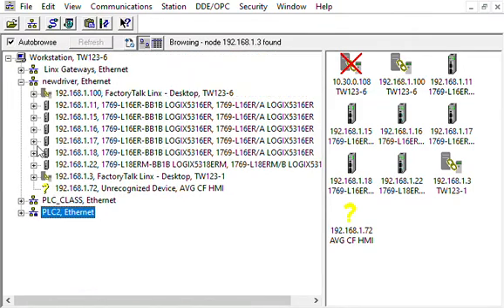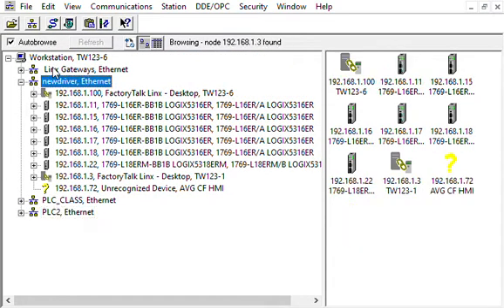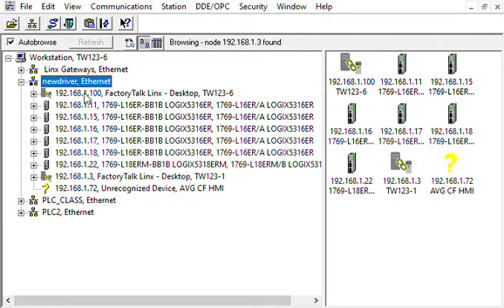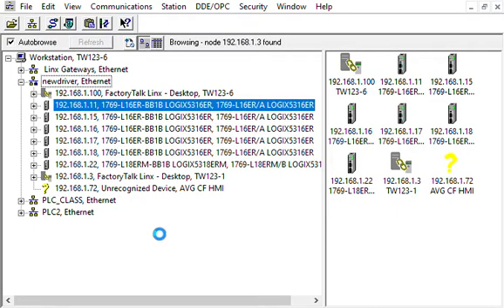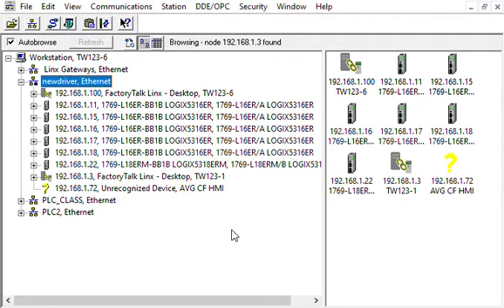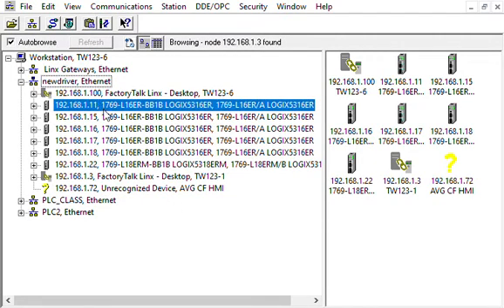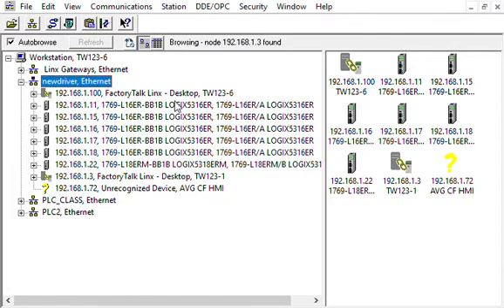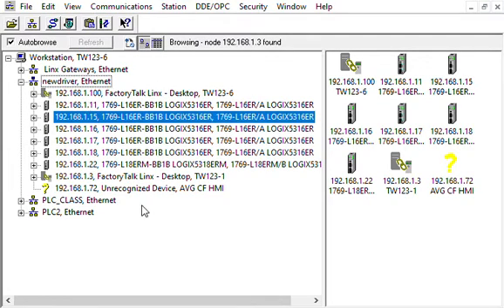So let's close that. Let's go back to this one. While I have this open, one of the nice things about it is I can right click on this first one. For example, I can go and get some device property information about the controller. It'll tell me what firmware it's got, information about it. I can also right click and click on data monitor. What data monitor does, it goes and pulls the information from the controller. You probably saw that pop up. Let me do that again on a different one.